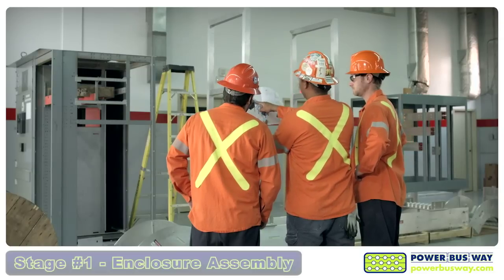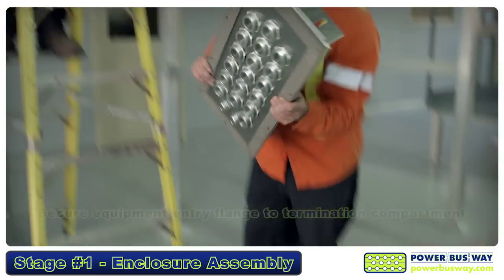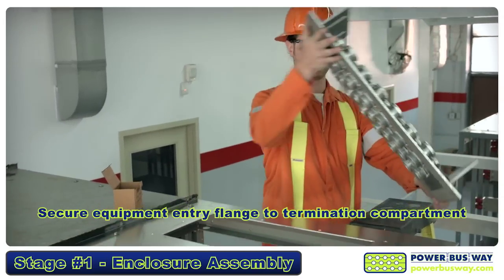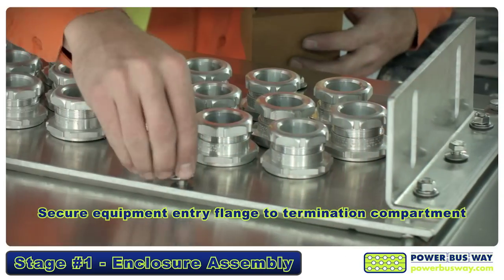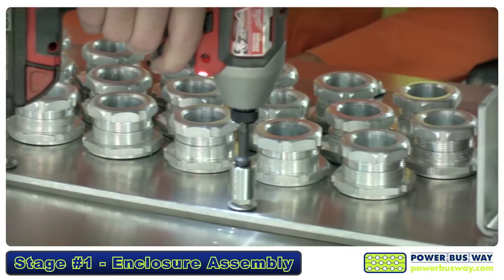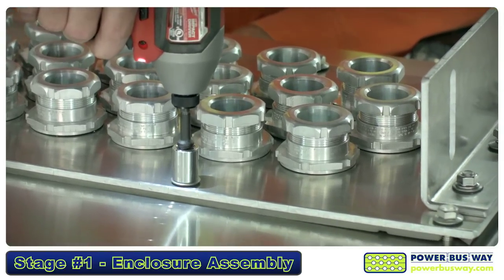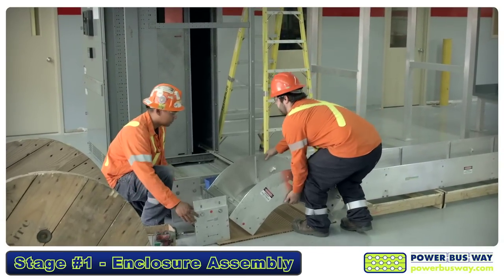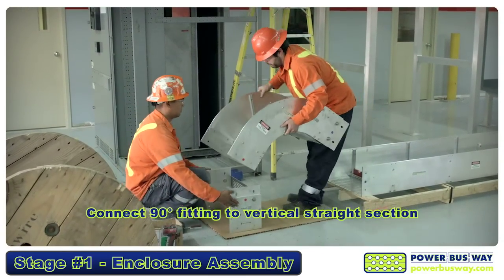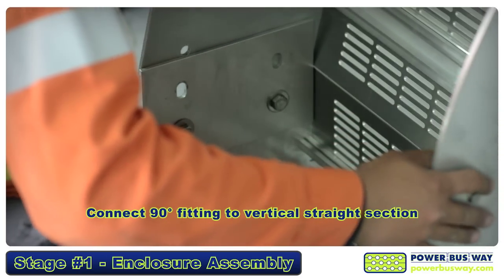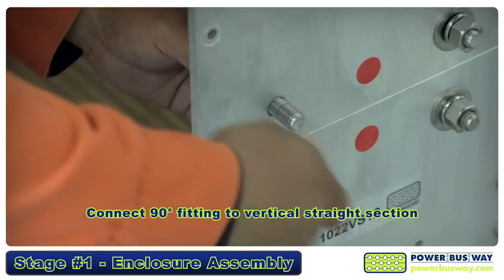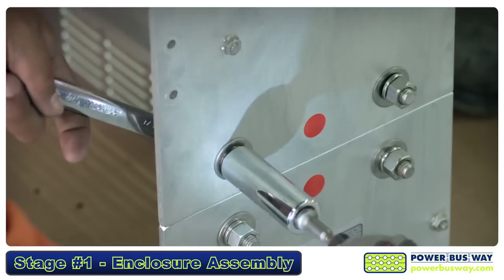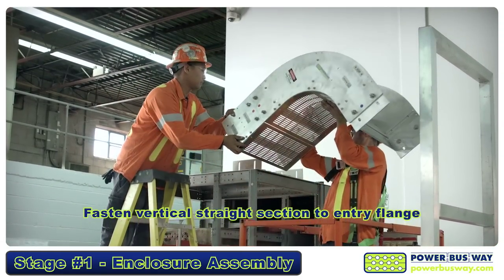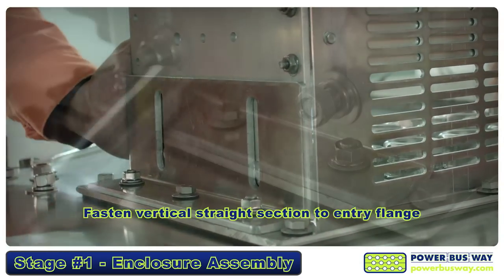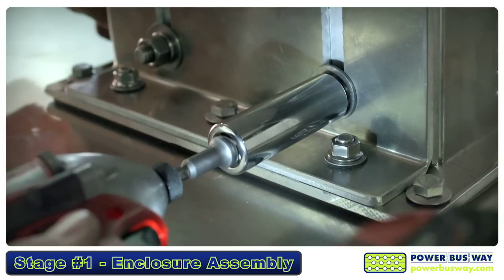Let's begin by assembling the cable bus enclosure. First, secure the equipment entry flange to the first termination compartment and fasten all of the mounting hardware. Ensure that the flange is secure and the gaskets are compressed. Next, using the color coding or identification labels, position the 90-degree fitting atop the vertical straight section. Slide both pieces into position and fasten using the corresponding hardware. Once firmly connected, mount the vertical straight section atop the equipment entry flange. Position the two properly and bolt them into place.